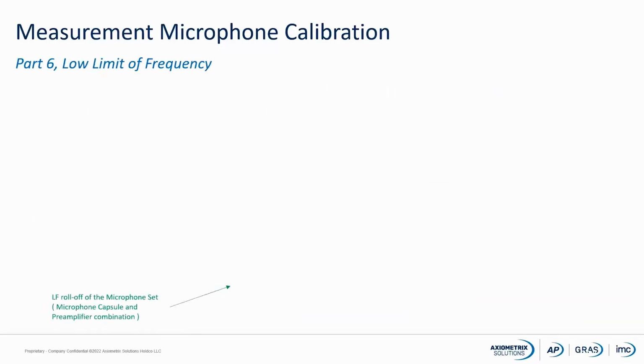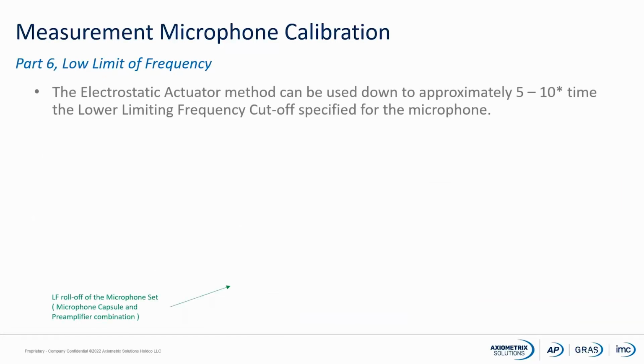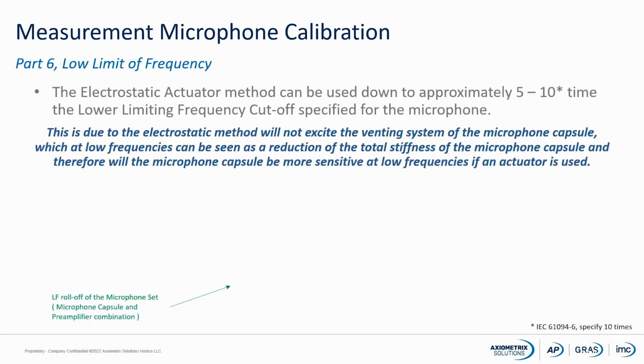If we look at low frequency limitations, as I mentioned before, the electrostatic actuator can be used down to approximately 5 to 10 times the lower limit frequency cutoff of the microphone. This is because the electrostatic method will not excite the venting system of the microphone capsule, which at lower frequency can be seen as a reduction of the total stiffness of the microphone capsule, and therefore the microphone capsule will be more sensitive at lower frequency if an actuator is used.